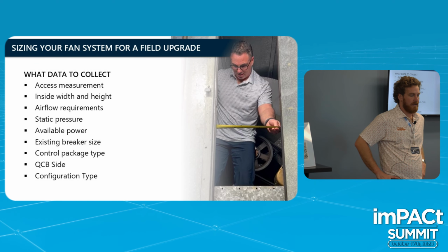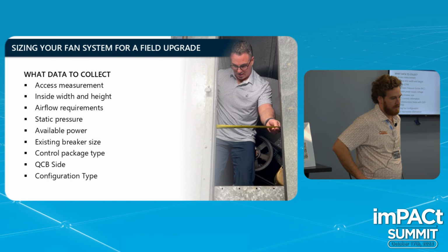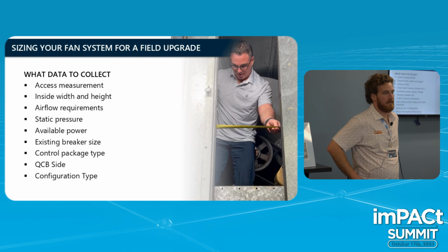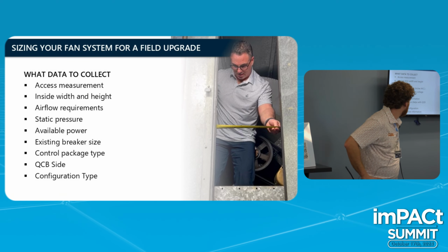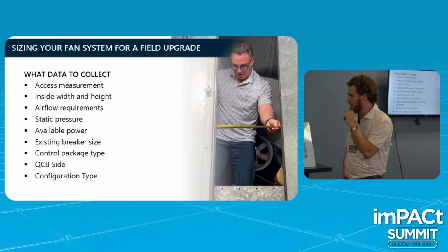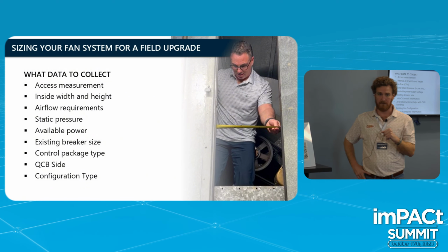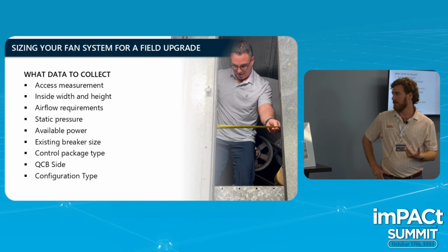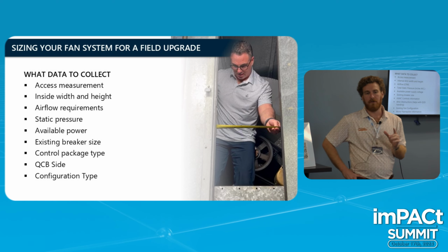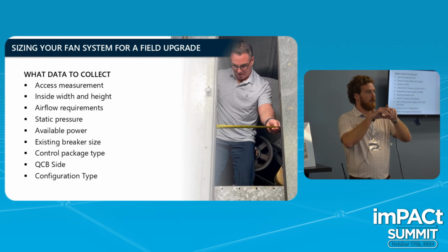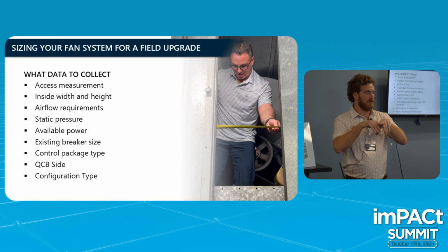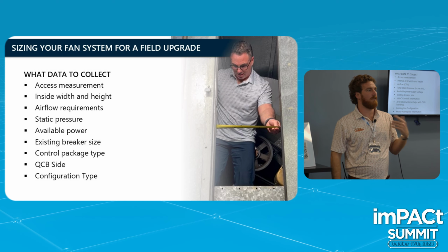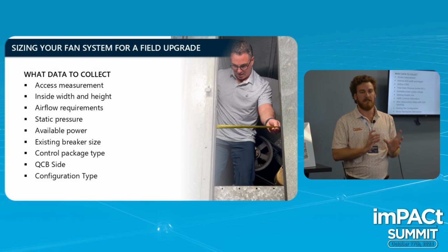So if you're working directly with the contractor or with the end user, you definitely want to get that information. In situations where you don't have the static pressure or the airflow, there are some methods we have to calculate them. If you don't have the airflow, you can typically measure the coil face, and then say, all right, that coil face times 500 feet per minute is a good approximation of the CFM.